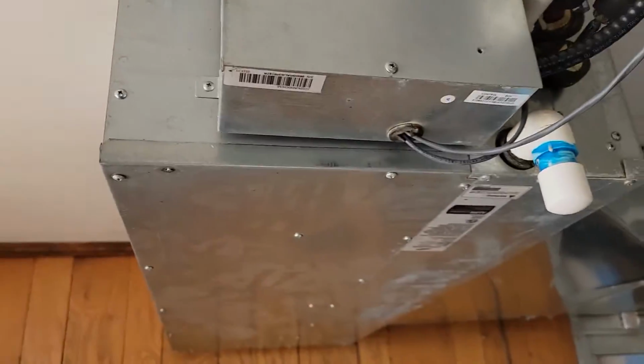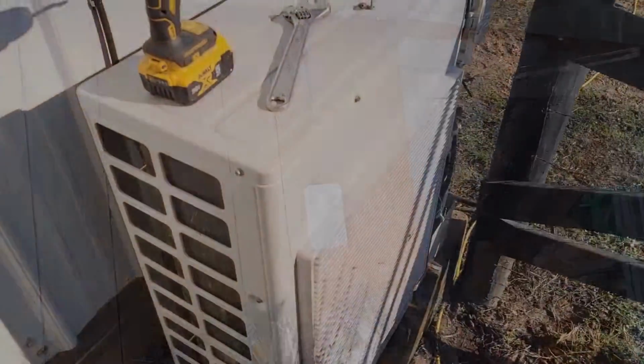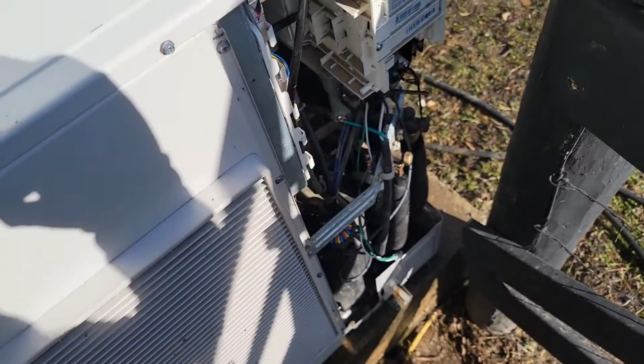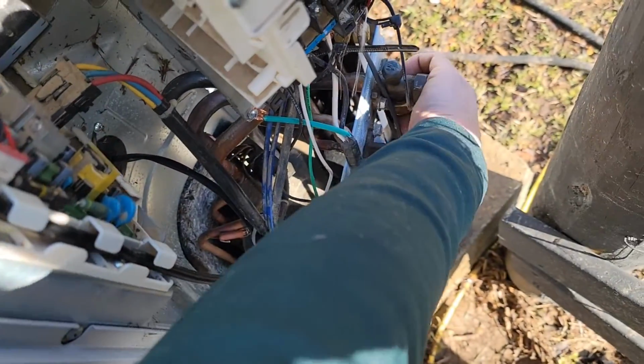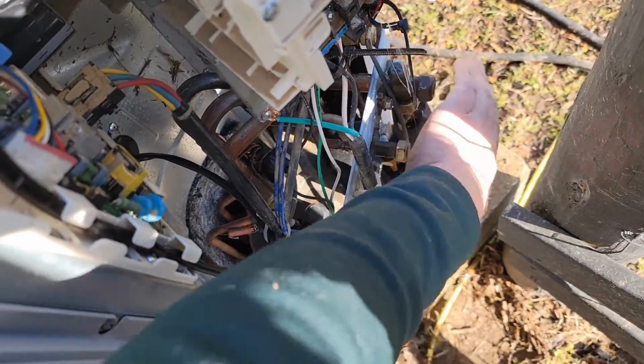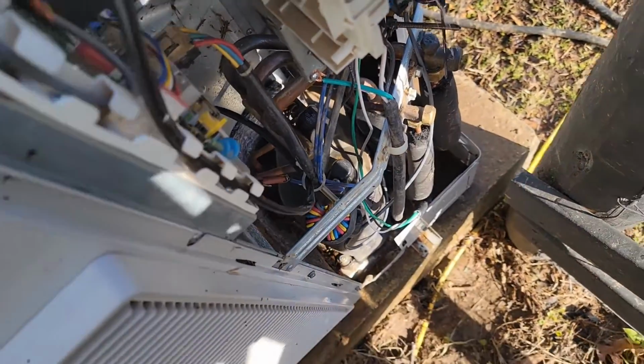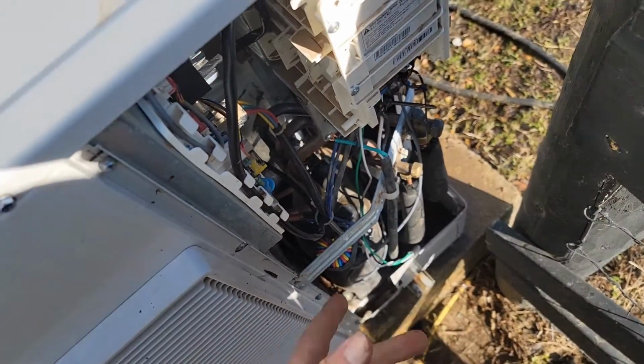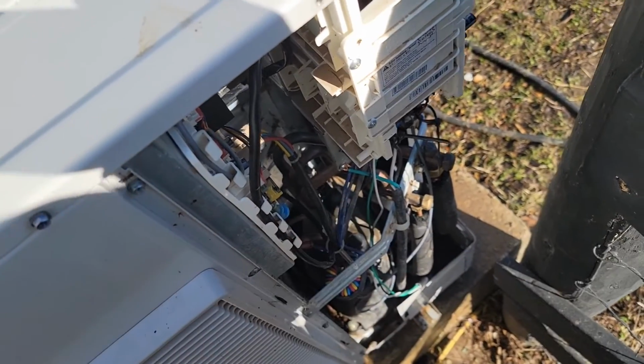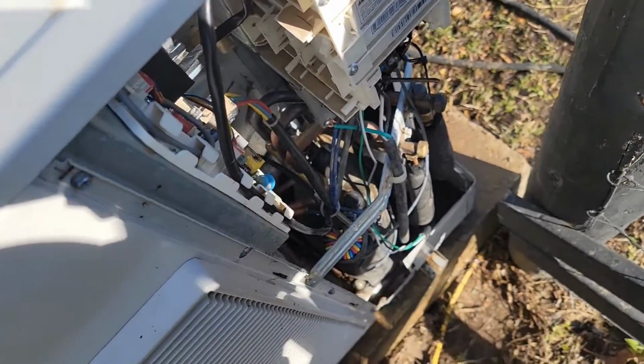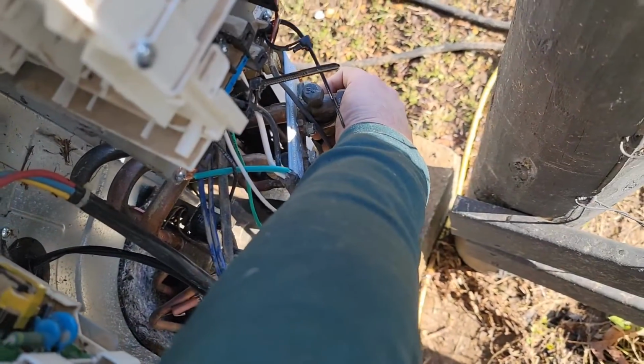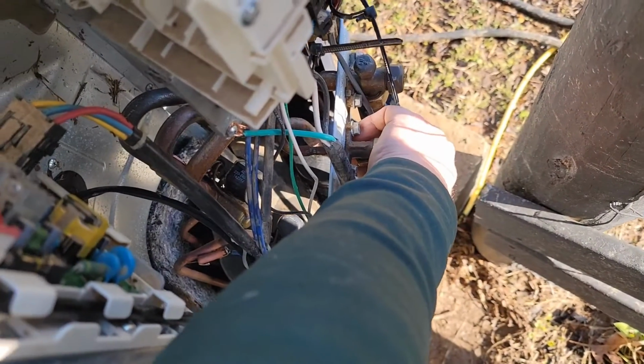So let's go outside. Let's take a look at that condenser. Okay, sounds pretty good. Now we need to put our gauges on here, measure the temperature of this vapor line. Should be around 300, sometimes 350. Make sure that it's nice and warm, and then that indoor coil, that heat exchanger, will start to heat up.